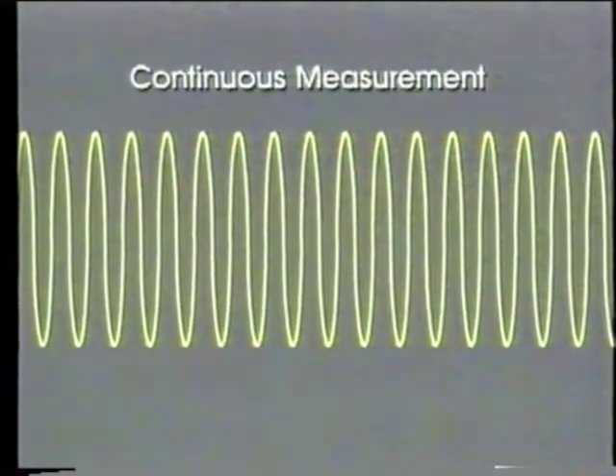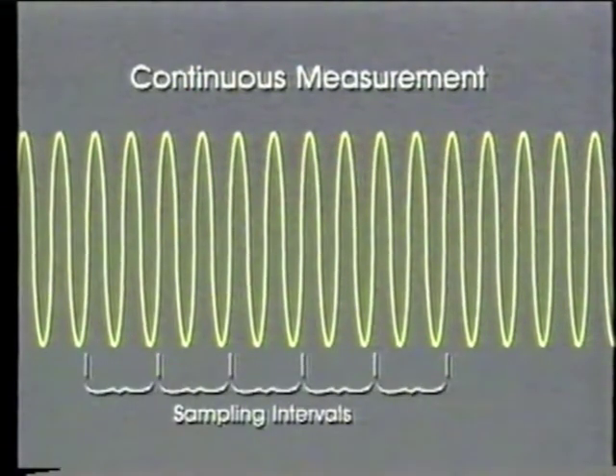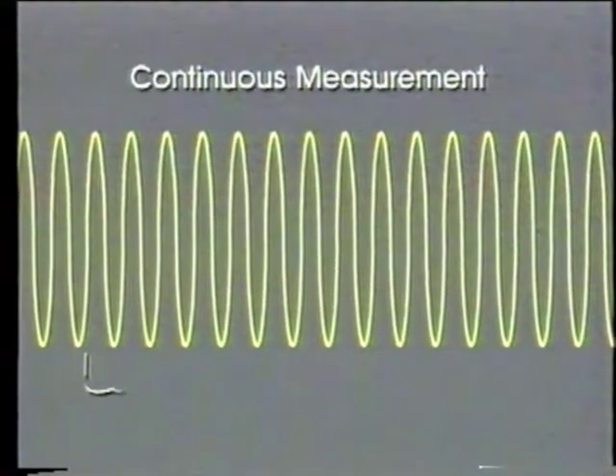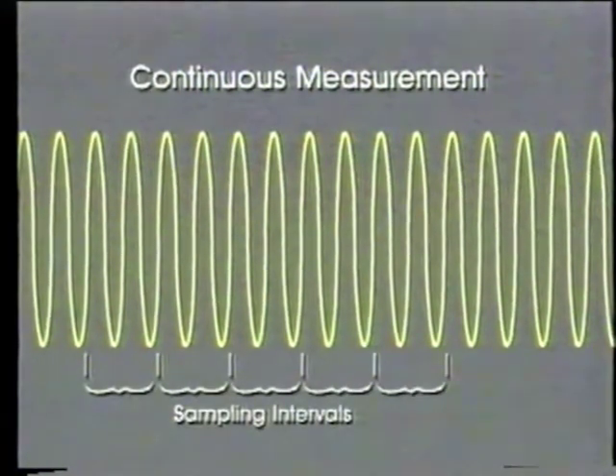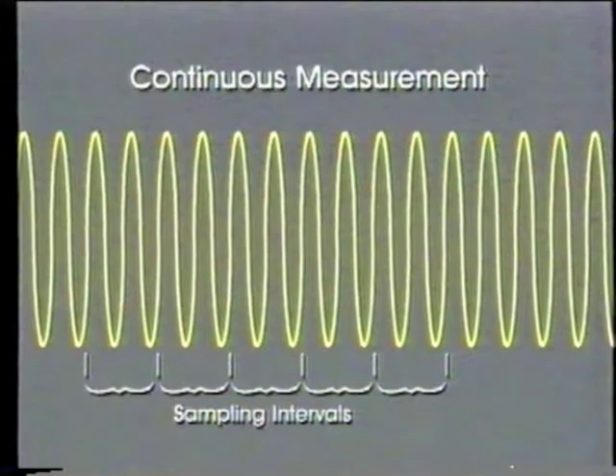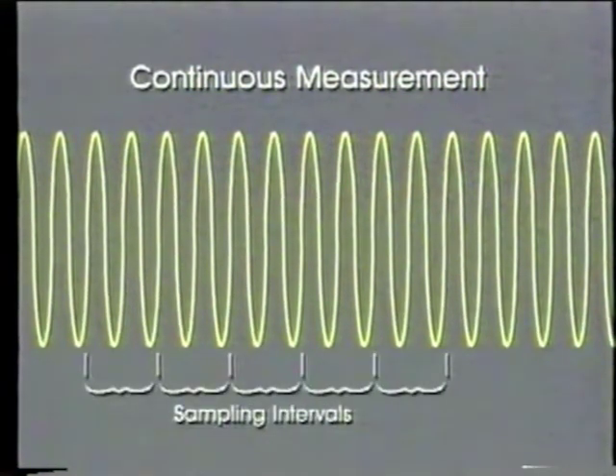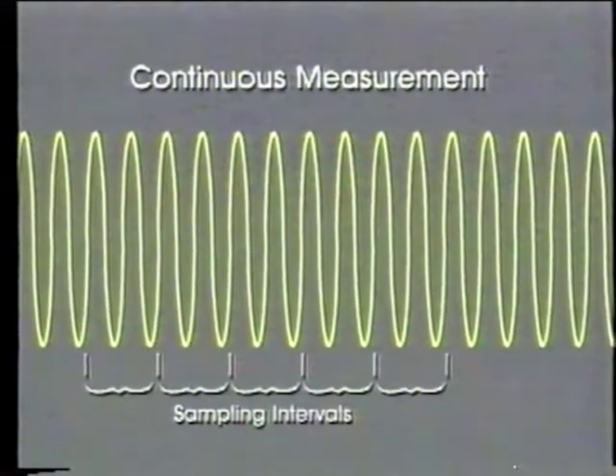With continuous measurement, however, the 5371A can make frequency measurements back-to-back with no dead time. Processing is done after the measurement block is complete, up to 1,000 measurements later when using the 5371A to analyze the data, and up to 4K when using a computer.